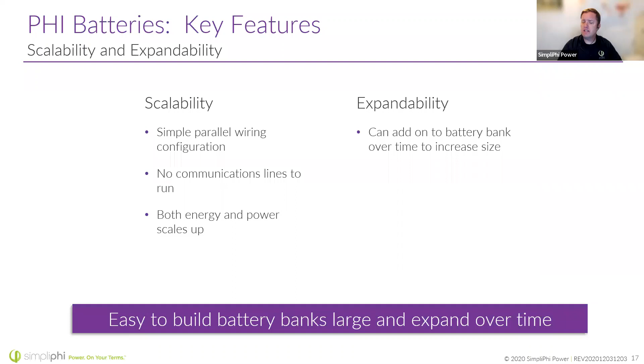You want to be sure to always make sure that any of the new batteries you're adding to the system has a voltage within 1 volt on 48 volts of the old batteries. That way you're not going to see a lot of voltage or current flowing between batteries if they don't have a close voltage.